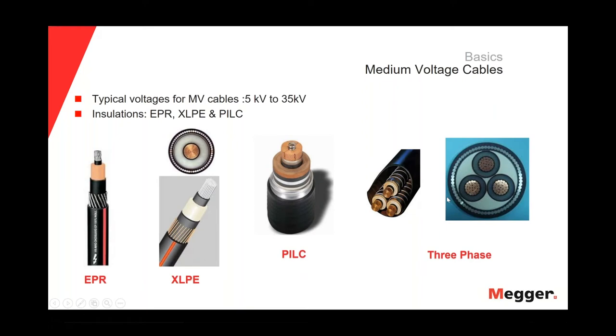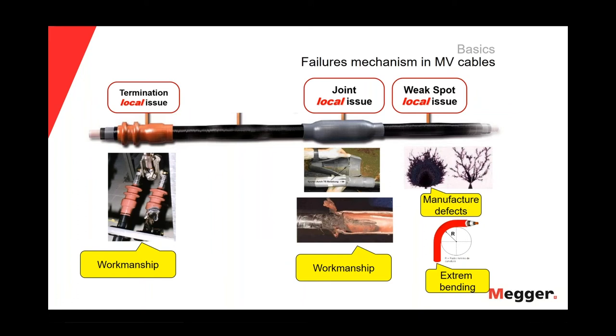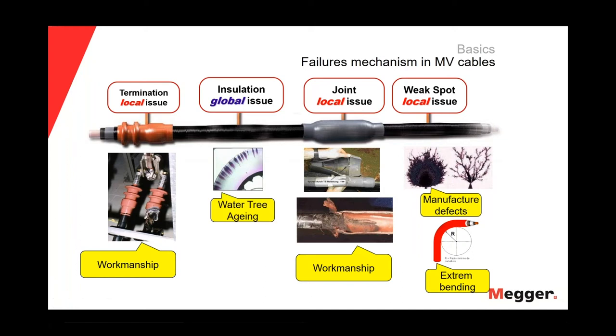Okay? So in terms of the failure mechanisms for medium voltage cables, we should distinguish between local issues and global issues. Local issues we will find mainly in terminations and splices, and typically they will be workmanship problems, but also manufacturer defects as well. Basically, those are single points, an area of weakness of the cable. On the other hand, the global issue in the insulation is distributed water trees in the entire length of the bulk insulation. In the case of XLPE cables, that is the global issue; in the case of paper impregnated cables, the global issue will be the cellulose degradation. So it's important that we distinguish between local issues and global issues.